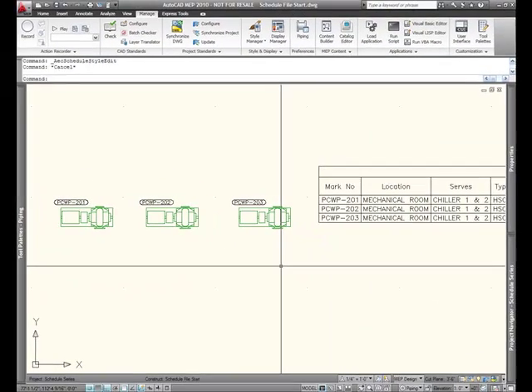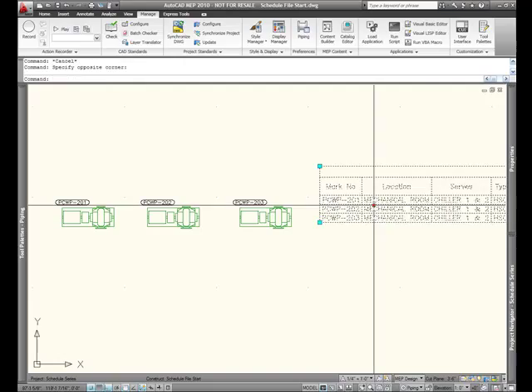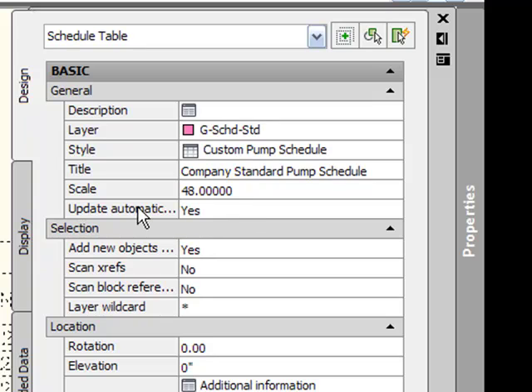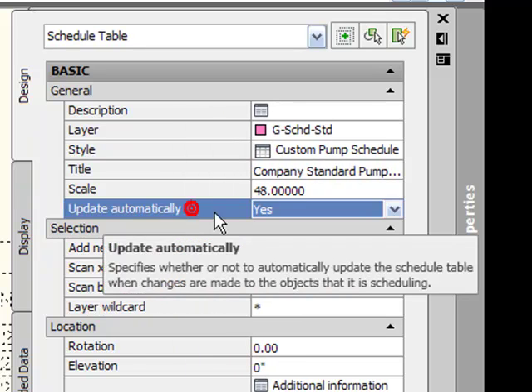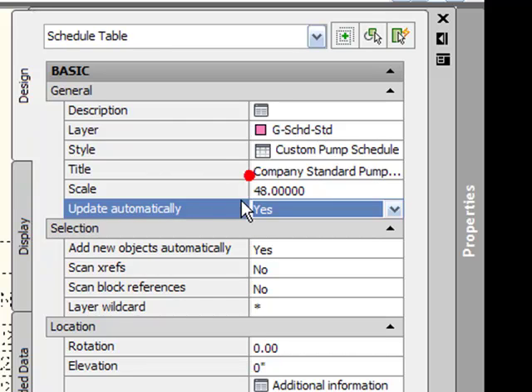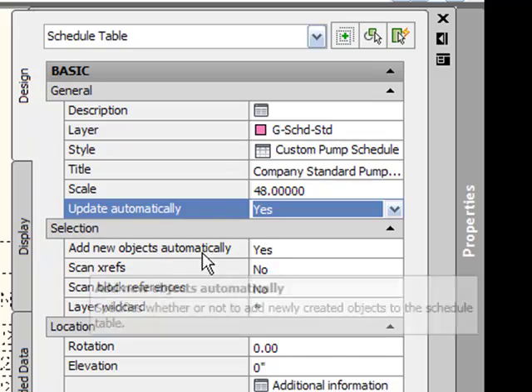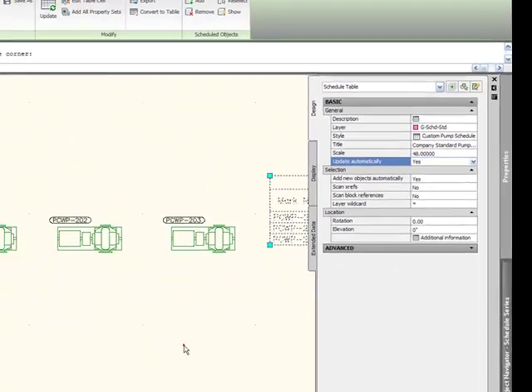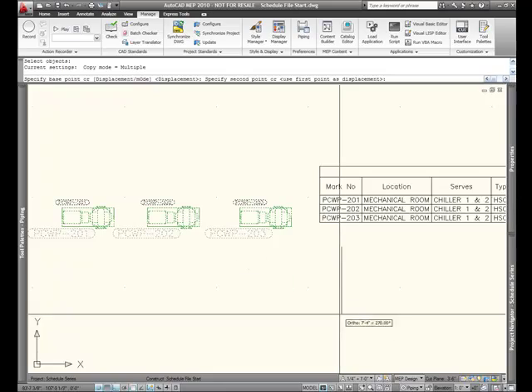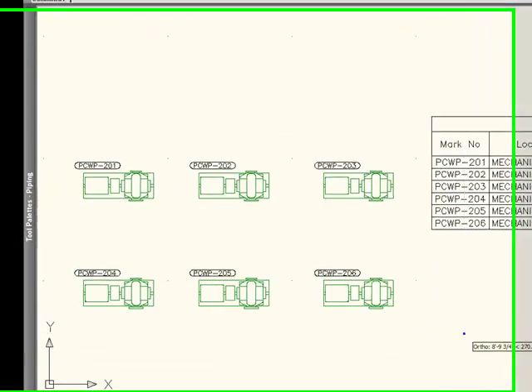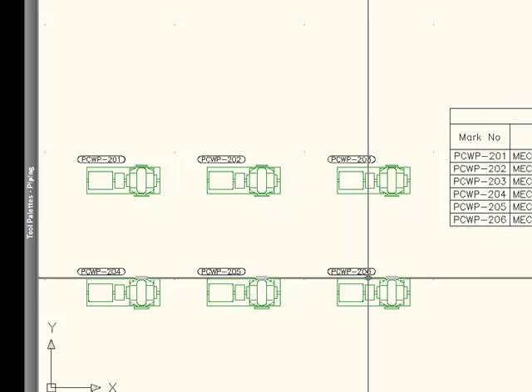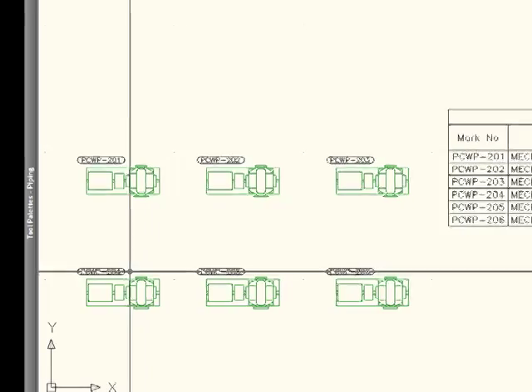Now, there's a whole lot of clever things that we can do with schedules in particular. If we take a look at the properties here, I just kind of want to focus in on one thing. I want to show you that this schedule automatically updates. That's currently set to yes. And just down below, it will also automatically add new objects. That's also set to yes. Watch this. As I copy this down, my schedule has updated. So, now I can see 201 through 206. And also, my tags have automatically incremented themselves.